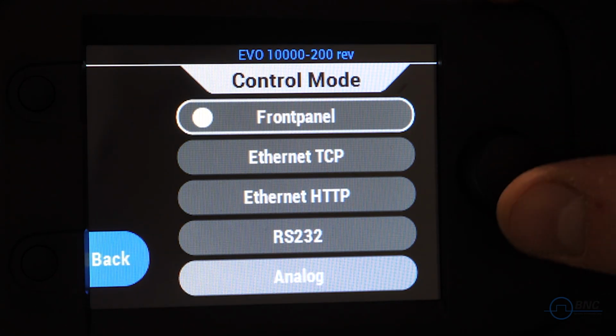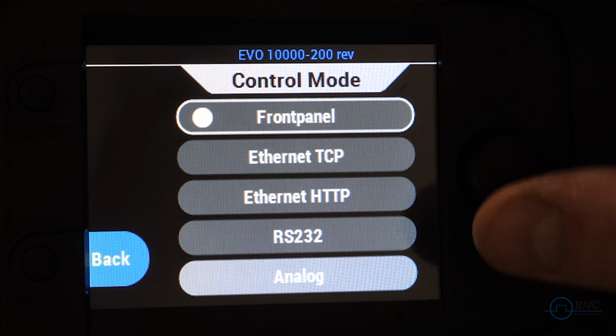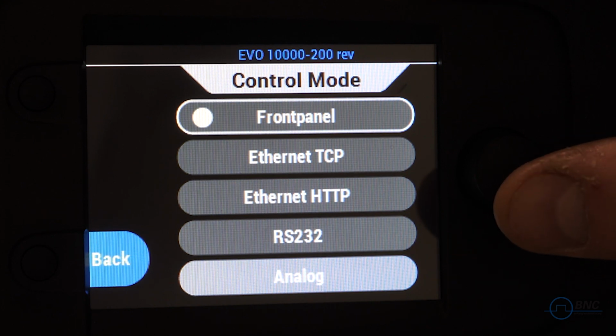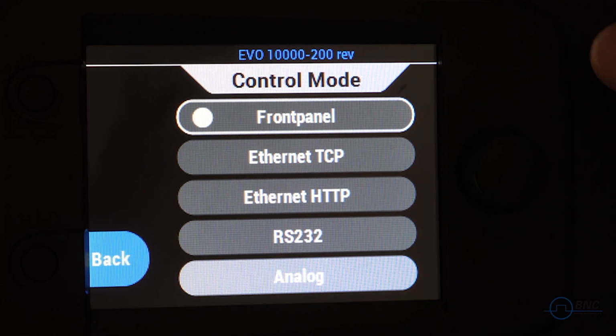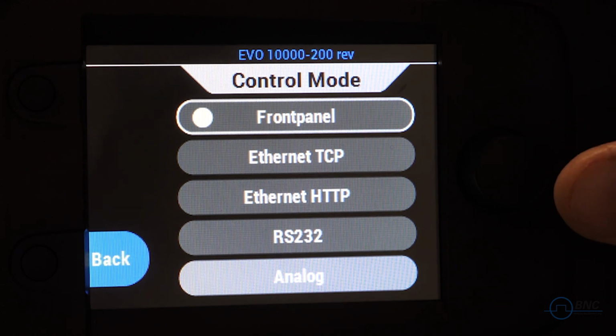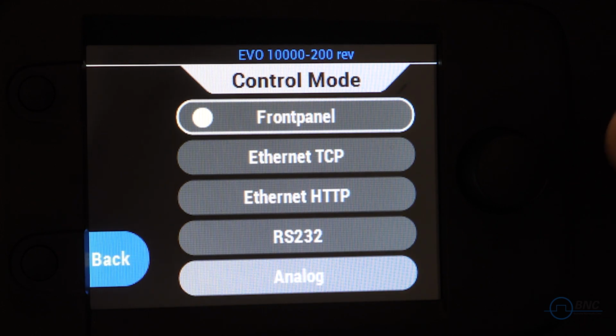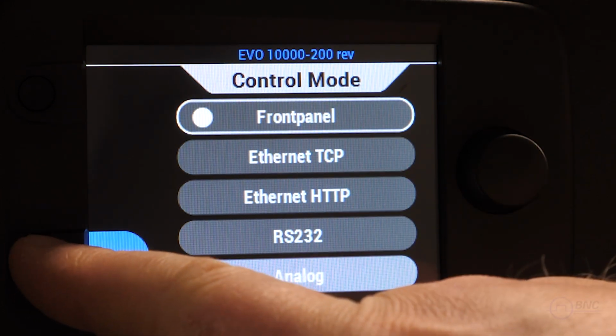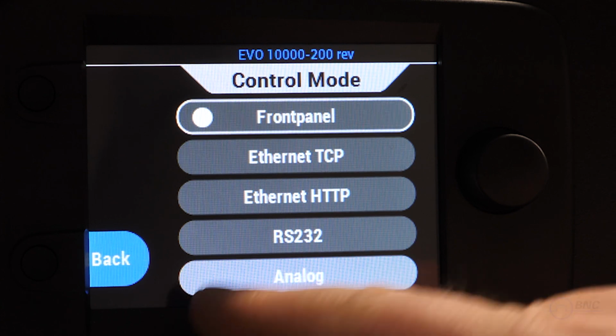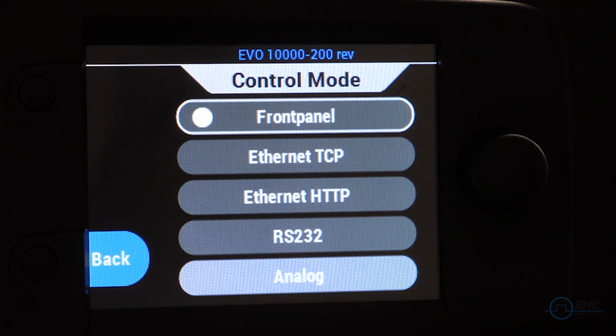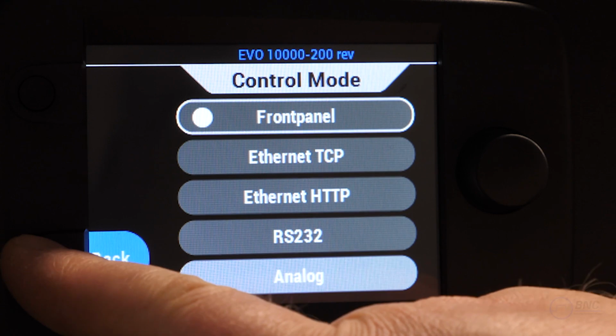Here we can select how we're going to control it externally. Right now we have it set to front panel control, but we can change that to Ethernet, or Ethernet HTTP if we're using the web interface, or RS-232. This particular unit does not have analog control installed, but it's also possible to control the output high voltage with a small analog control input voltage.